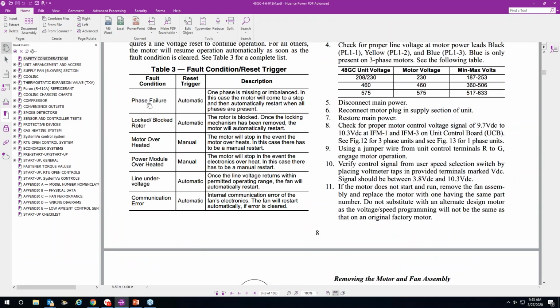Let me shift here and go to the book. We'll go to these fault codes and some of the things that can happen. So phase failure, locked or blocked rotor. This can happen in one of two situations. Either we're outside of the rated voltage range on 460 volt units, and by that I mean if we've got voltage supplied to the unit that's upwards of, say, 502, 504, right up there at that max voltage range, we're seeing the motors lock up. So you can give the motor a little spin, and be very careful doing that, obviously, or cycle power to it and it'll unlock. But if we have continuous high voltage, it will just play heck with these motors.